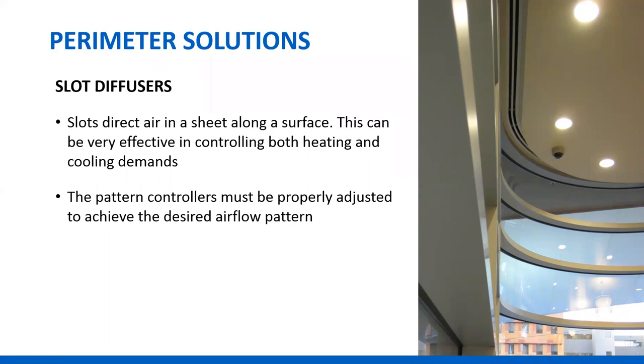The answer is not the balancer. Even though some requirements say the balancer should adjust slot diffusers, typically they won't — first because they don't know how it's supposed to go, and secondly because they typically don't have the time in their budget. We walk into spaces and see a lot of improperly adjusted pattern controllers at the perimeter. Ideally, the slot next to the window should be set to blow air towards the window, and the slot away from the window should blow air into the room. If all the slots are set to blow down, the room is going to stratify.